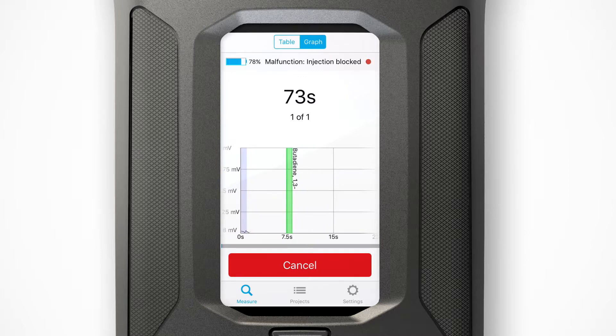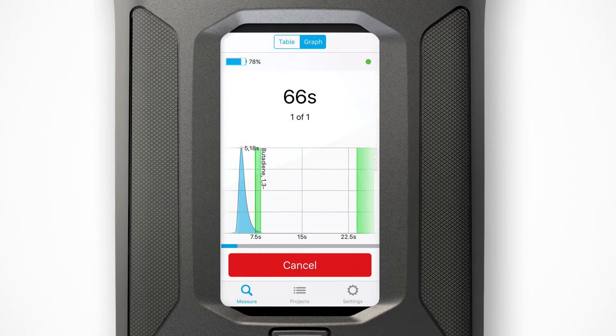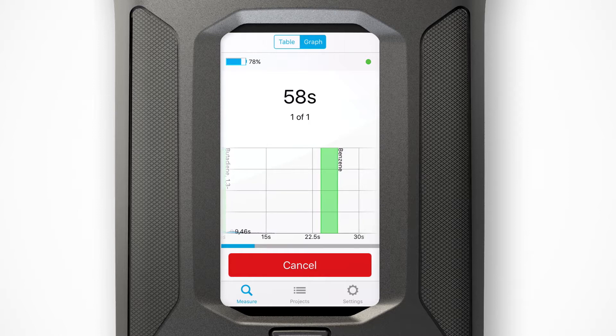In analysis mode, start measuring the presence of selected target substances. Within just 30 seconds, the XPID detects individual gases based on the time it takes each gas to flow through the separation column. A real-time chromatogram shows you the analysis as the device measures.